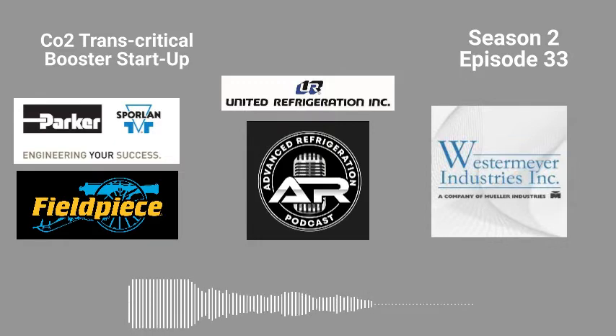So before I pull vacuums, I put all the transducers on, and I get them all reading and all set up, make sure they're all reading. And then I make sure that none of them are leaking with pressure on them before I pull vacuums. And I'll go around and valve them all on, because that is the number one thing. You want to make sure they're all valved on and reading pressure on the nitrogen before you do anything. So once you get everything pressure tested, let it sit for 24 hours. Pray to God you aren't chasing small little tiny leaks on transducers and packed angle valves and coils that aren't brazed up completely that somehow made it out of the factory.